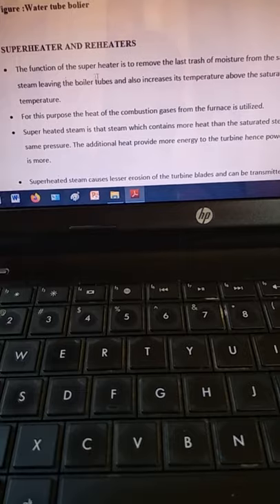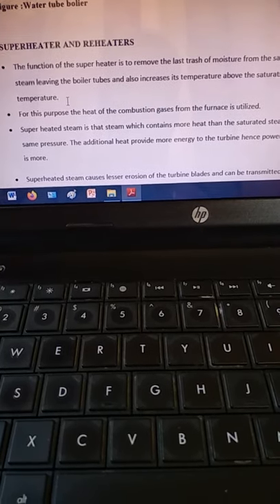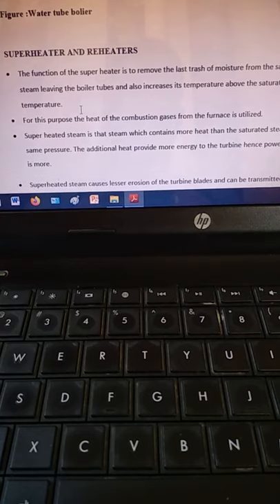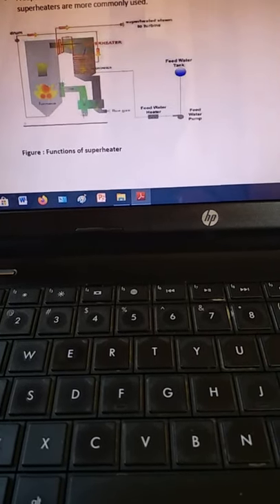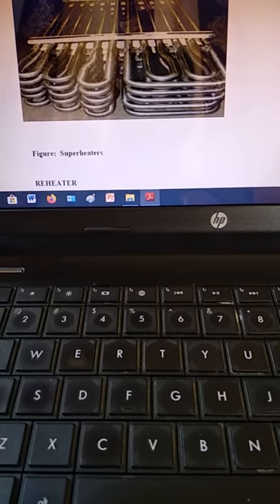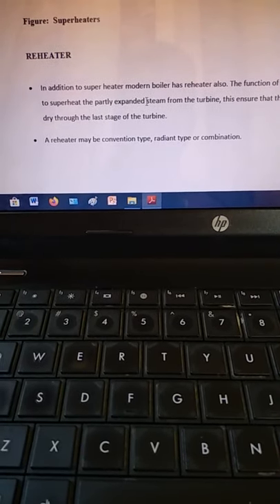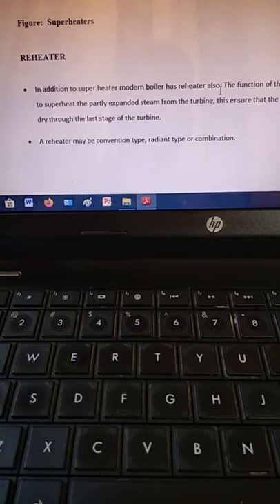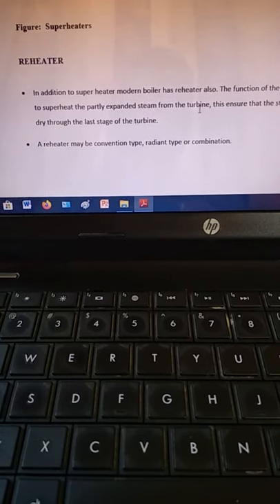The function of the superheater is to remove the last traces of moisture from the saturated steam leaving the boiler tubes and to increase the temperature above the saturation temperature. Superheaters and reheaters are boiler accessories already discussed. Modern boilers also have reheaters — after coming out of the superheater, steam is reheated again so there is no moisture, making it fully dry to prevent turbine blade erosion.